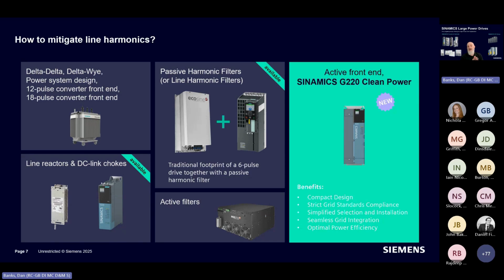But the other solution that can be much neater in the drive world is a clean power drive, or what would traditionally in industry be called active front end drives. The benefits of using an active front end solution really is it's a simpler install, single box, cables in, cables out, happy days. No messing around with multiple devices in your panel. Often designed to give a clear compliance with a particular standard. Usually very power efficient in the way they do things.